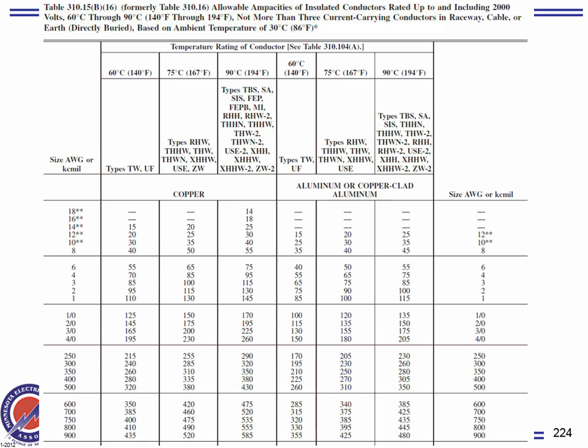I have a couple of rules, guys, on how to use it. But before we use the rules, I want to remind you that these are the temperature ratings of the conductor: 60, 75, and 90. Now all the conductors underneath are rated accordingly. For example, let's just use this one, a conductor rated for 60. If you put two H's in it, THHW, that becomes 75. If you put THHN, that will get you 90.